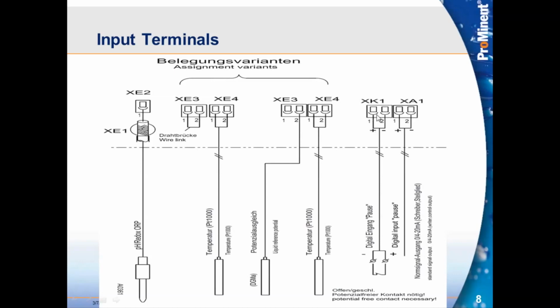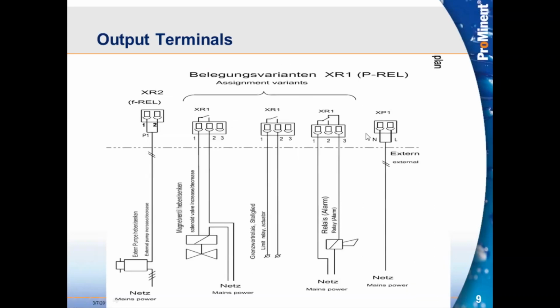XK1 would be our pause input. So that is the signal coming from our flow switch in the DGMA. And then XA1 is our milliamp output. So we can have that assigned to either, again, be a measured value signal out or a control value signal. Another variation of wiring, we might see the pump going to a frequency relay. So now it's being slowed or sped up depending on where we are in relationship to our set point. Here, a variety of XR1 outputs. XR1 in this case is going to a solenoid valve. So we would use 1 and 2 to energize that, 1 being the common of that 3-pole output.